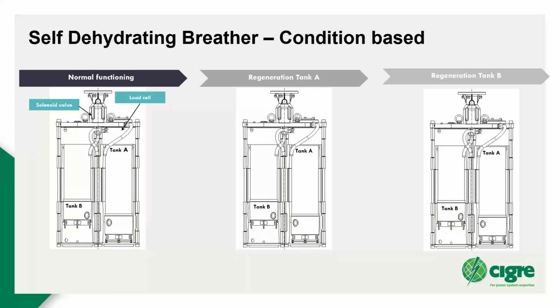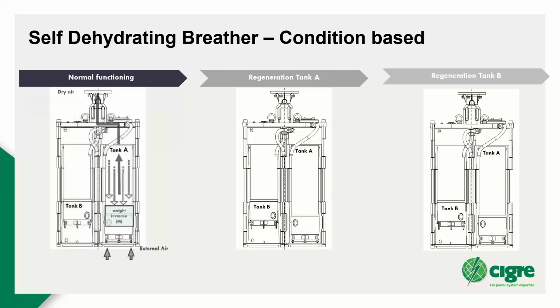In this example, I have taken the condition-based self-dehydrating breather. Here we have 2 tanks, tank A and tank B, and there is a valve which closes the path for either tank A or tank B, and a load cell which measures the weight of the silica gel. When it is breathing through tank A, the weight of the silica gel increases and the load cell measures that weight increase.